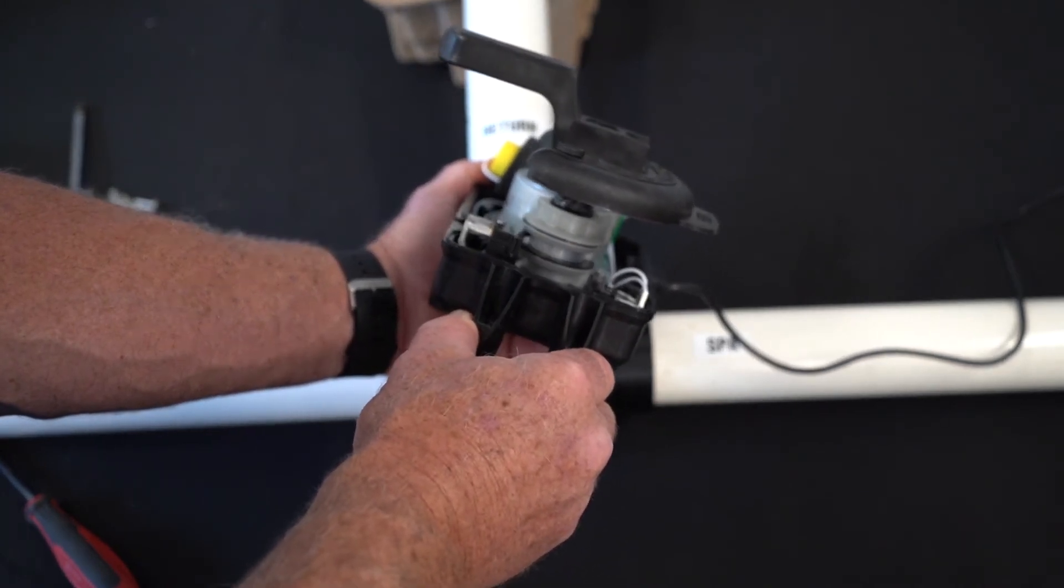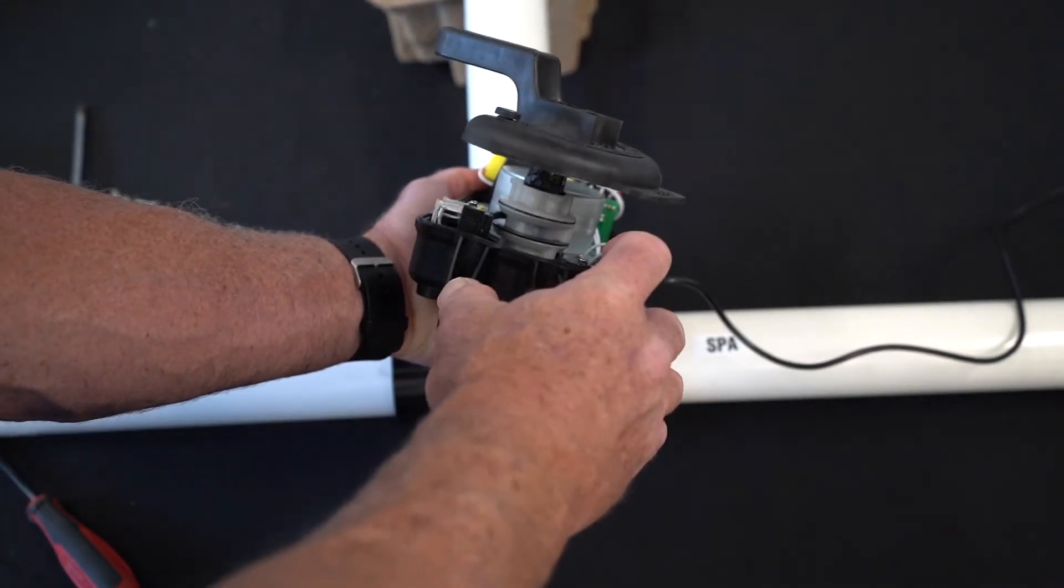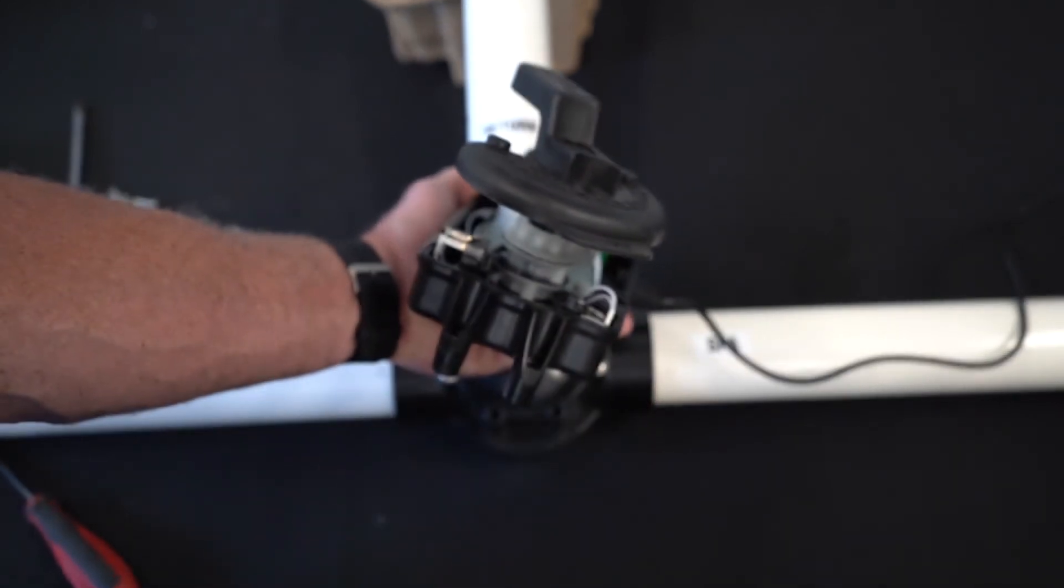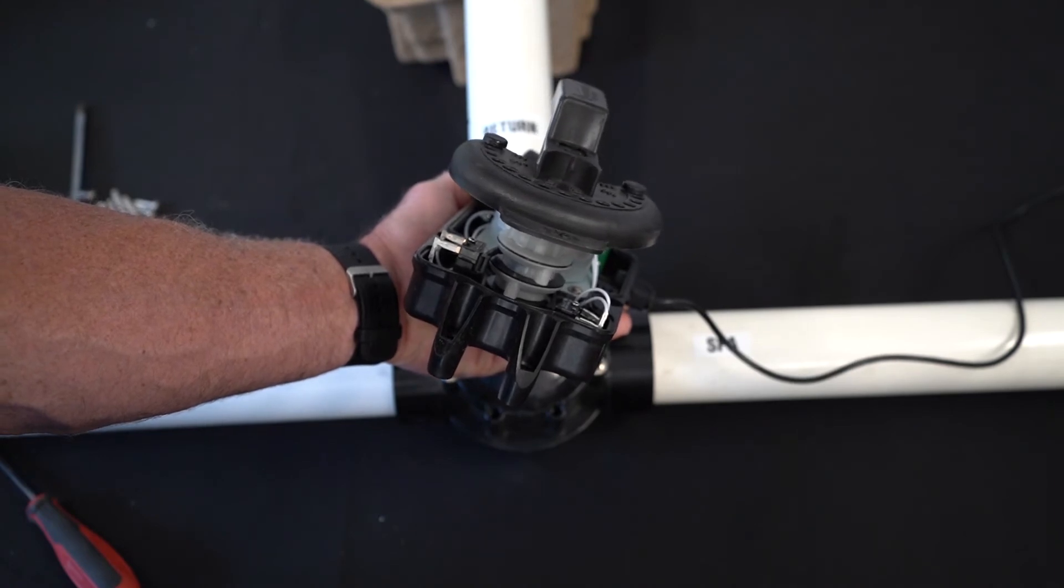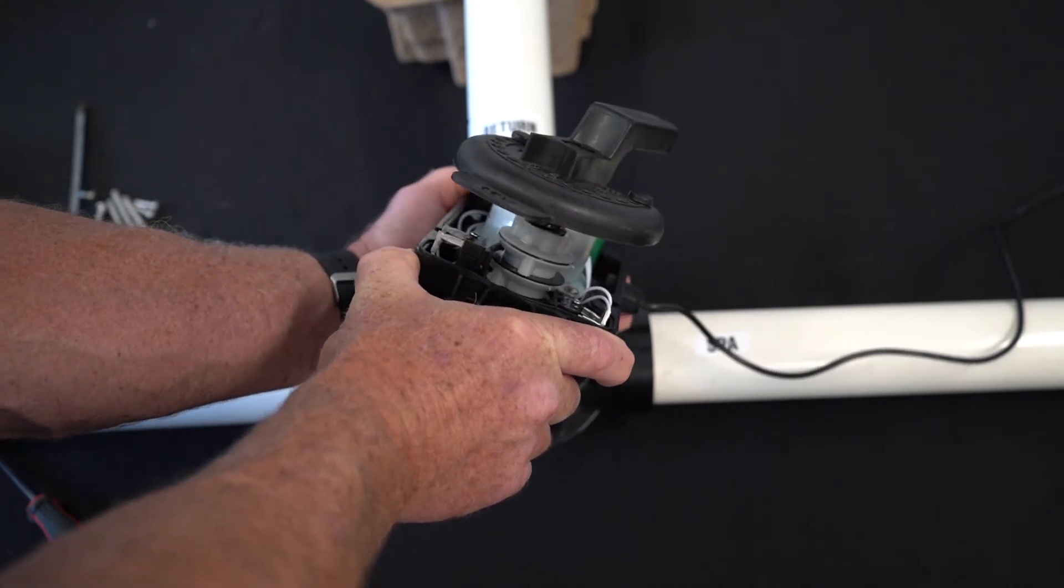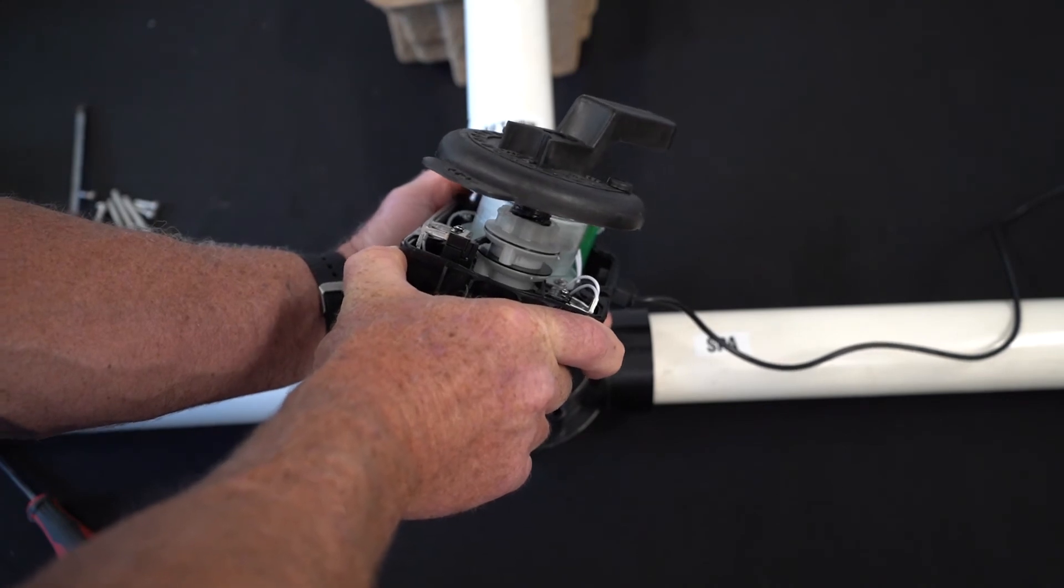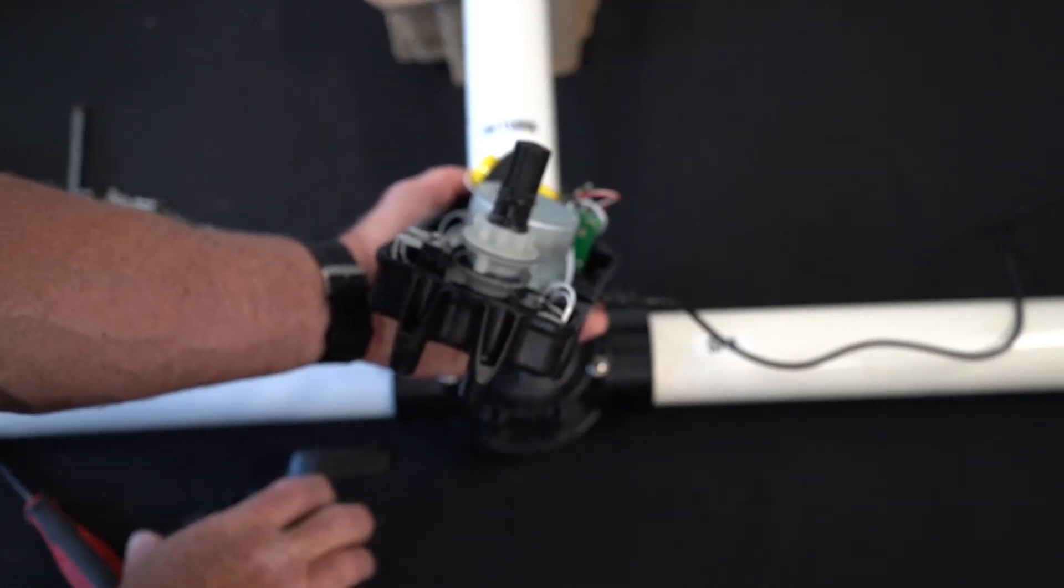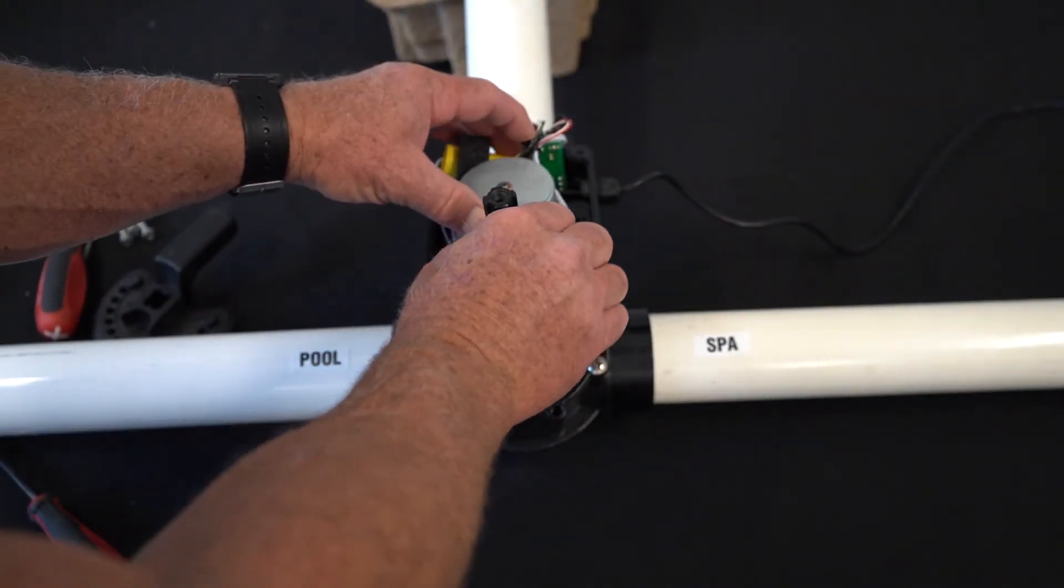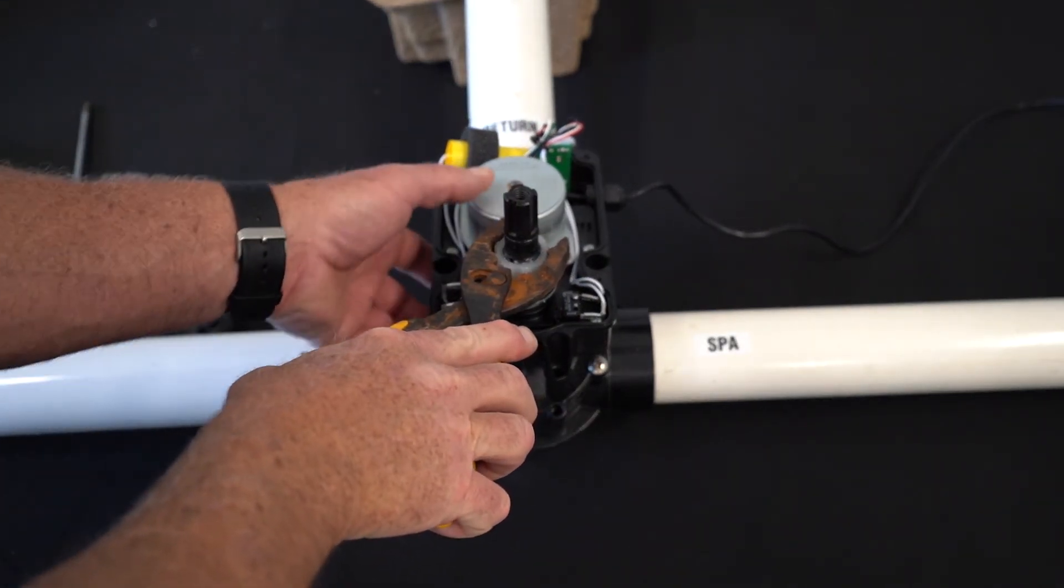So we're going to want to set this cam up so that it shuts off the micro switch on this side much sooner than it came out of the box. And the way that we're going to do that is by adjusting that cam. So we go to the position that we approximately want. We're going to now come in and loosen up this nut right there. You will need to do that with a pair of pliers.